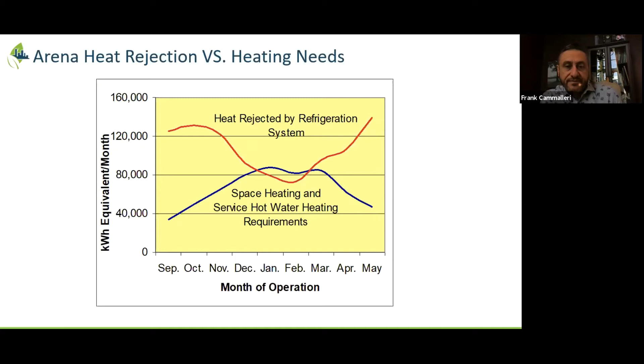But again, for the most part, the heat rejected by the refrigeration system is more than ample to cover the heat that's required in the facility, and most of that heat, we're finding, is typically provided by gas-fired boilers. So again, getting to that low carbon solution over time is to try to make use of the heat rejection and minimize the operation of any gas-fired heating. Okay.